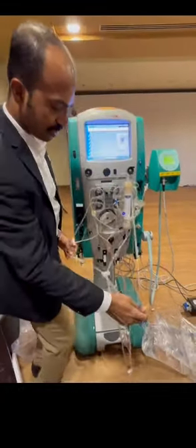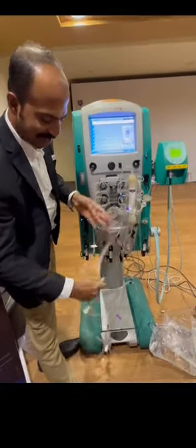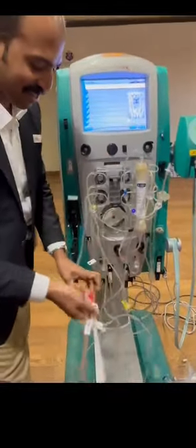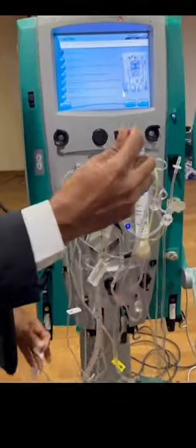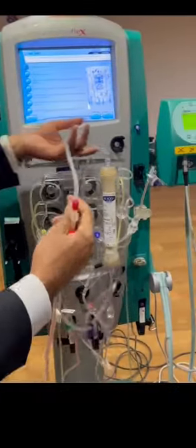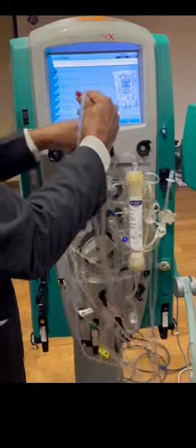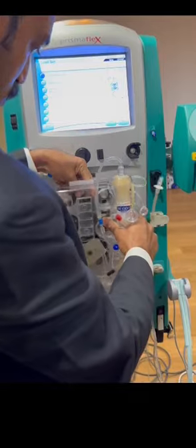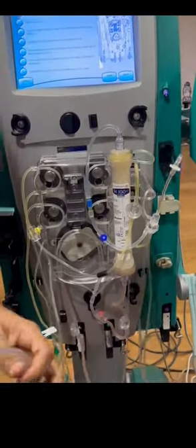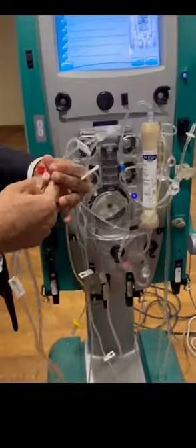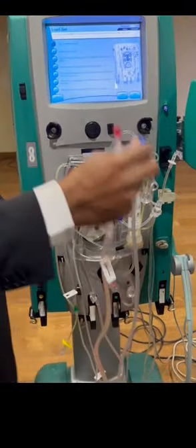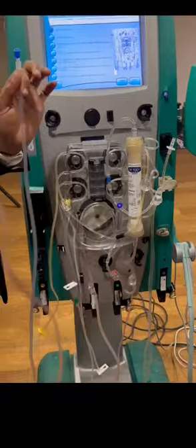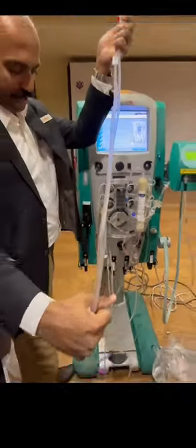This is actually for the technicians, but still I will show what all these lines are. We have a red line, which is called the access line. We have a blue line, which is called the return line. Usually in HD they say arterial line and venous line, but in this machine any alarm related to this line comes as an access line alarm, and this is the return line. These are the lengthiest lines in this filter.